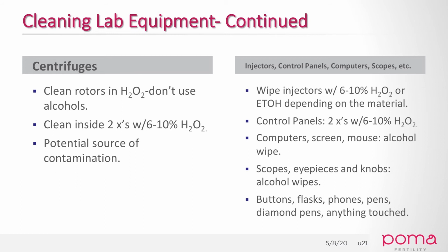Centrifuges are an area of great high potential, and the reason for that is centrifuges don't tend to get cleaned as much as they should be. If you do clean your centrifuges, though, make sure you don't use alcohol on the rotors. That's a big no-no. And clean the inside of them very, very well. I clean them at least two times with hydrogen peroxide because these are a great source of contamination.